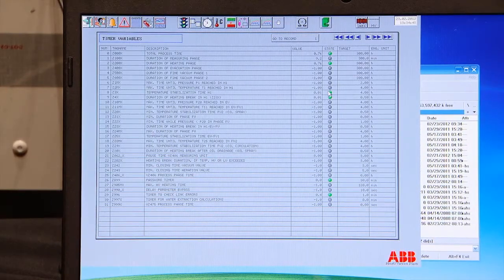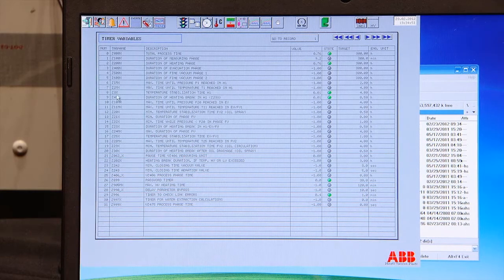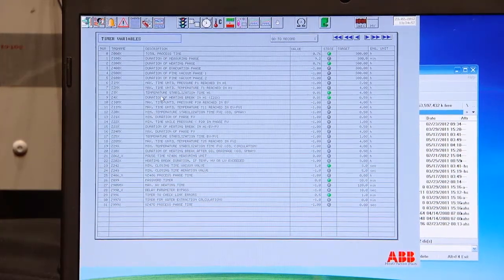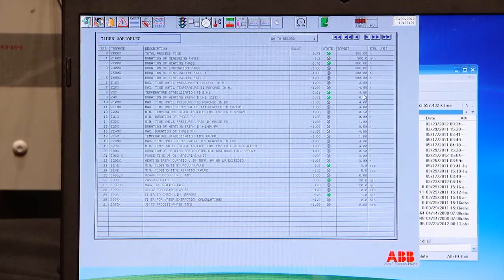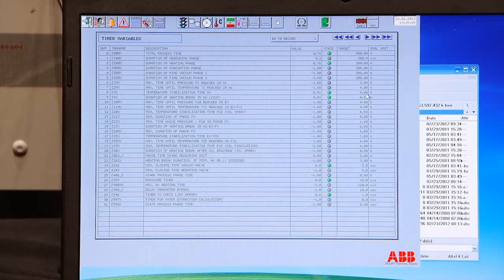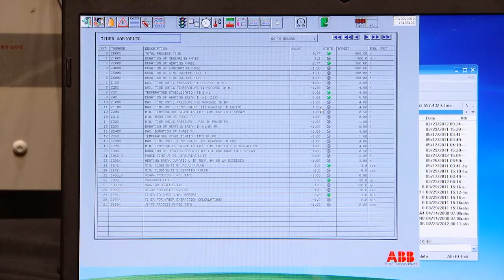We have now 2 new timers running. This is timer Z3X and Z4X. These are our stabilization waiting timers. They are in this example set to 4 hours and half an hour. This means that we are now waiting half an hour, doing nothing, waiting for the temperature in the transformer to stabilize. Radiation between the high voltage, low voltage, and to the core. So after half an hour, we'll take a new reading, take a new temperature measurement, and heat up again to our 65 degrees. When we're reaching 65 degrees, wait another half an hour.